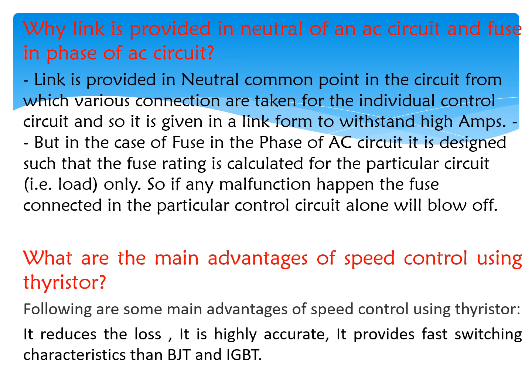Why is a link provided in neutral of an AC circuit and a fuse in phase of an AC circuit? Link is provided in neutral, the common point in the circuit from which various connections are taken for the individual control circuit, and so it is given in the link form to withstand high amperes. But in case of fuse in phase of AC circuit, it is designed such that the fuse rating is calculated for the particular circuit. That means the maximum load which can be allowed in that circuit.